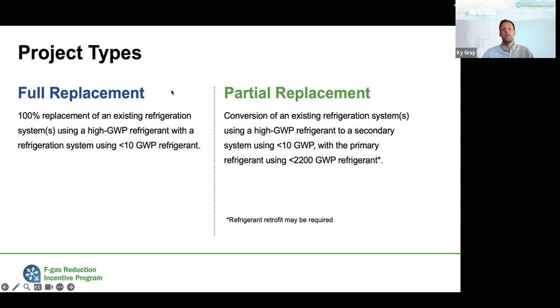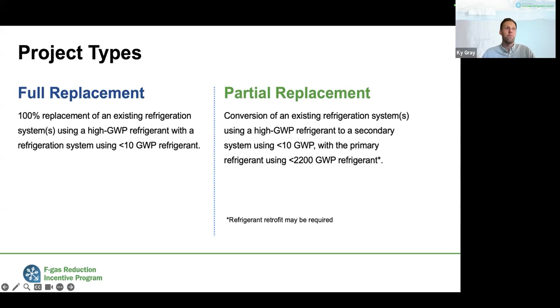This is a conversion of an existing refrigeration system to a secondary system. Essentially the fixtures, the cases, and the evaporators would be replaced, and the existing machine room, the high side, would be left intact with the addition of a heat exchanger. I'll let Ed do that a little more justice when he goes through the technology options in a bit.